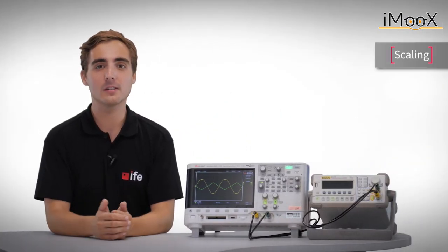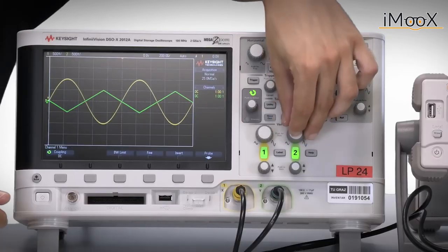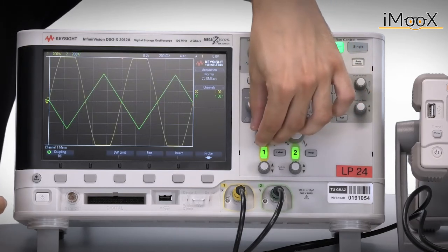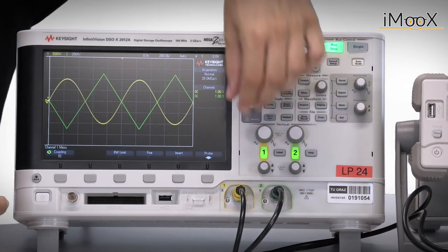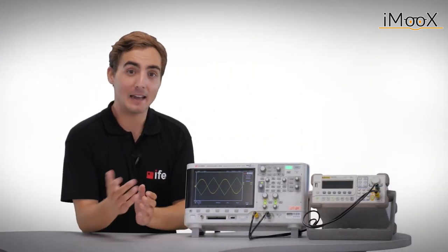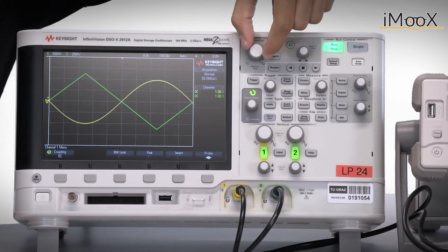However, the mentioned scale is not fixed. The voltage axis can be changed by the vertical scale control knobs for each channel separately, and as you see, also the volts per division have changed accordingly. The time axis is common for both channels. It can be changed by the horizontal scale knob.